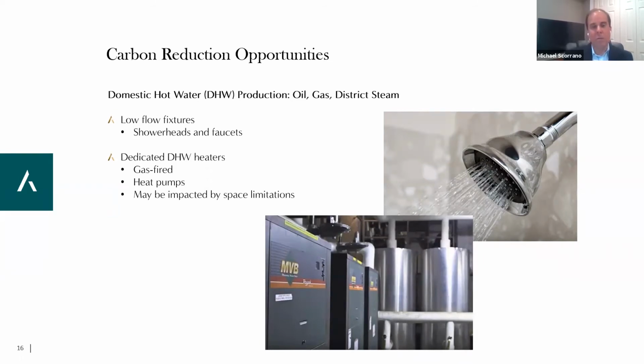In the boiler room, we like to put in smaller boilers to make domestic hot water. The heating boiler often has dual functionality — it makes heat in the winter and also makes domestic hot water year round. But that boiler, sized for the heating load, is way oversized for domestic hot water in summertime, and we see a lot of loss happen. So in many buildings we put in separate systems to run either just in summer or year round, since smaller boilers, because of their size and configuration, are more efficient than the bigger ones. That helps reduce energy going forward.